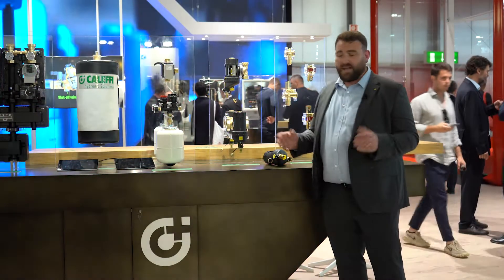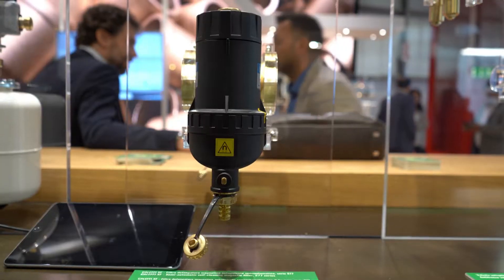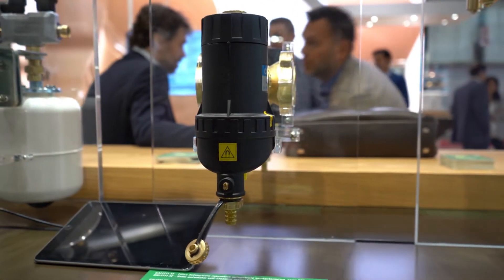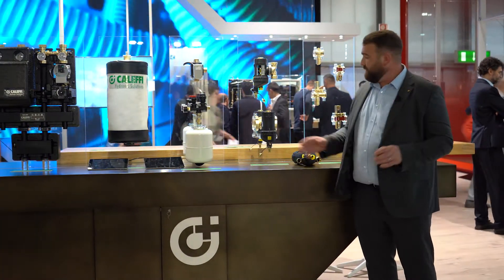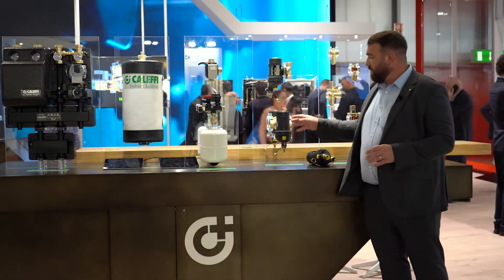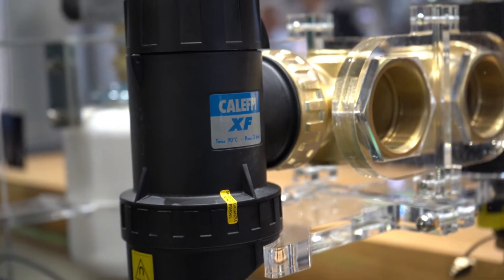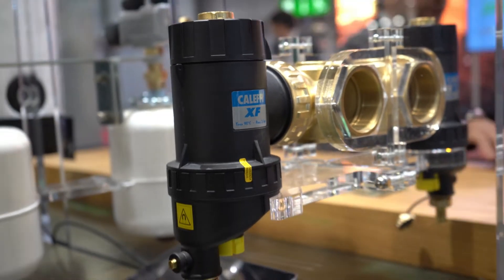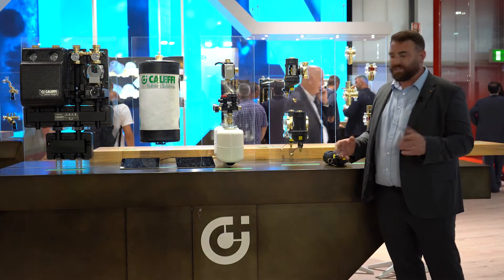Moving along, we can look at some dirt and air separation. Here we have the Caleffi XF — standard dirt and air separation with a filter and a magnet in there as well. But there's a really clever feature: the self-cleaning function. At the top of the valve you can rotate it, and there are internal brushes which clean the internal filter. It saves you taking everything apart, so you can maintain it very easily without shutting down the system.